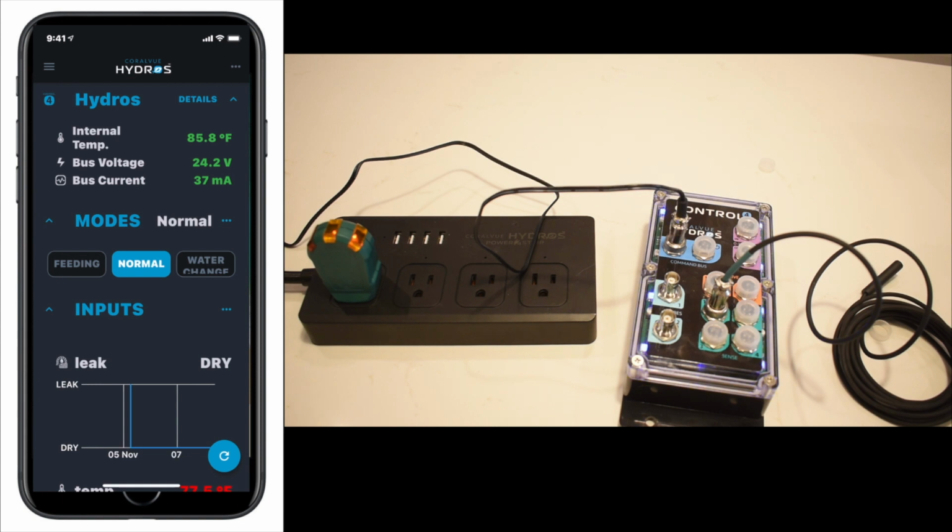The alerts come through really quick. So I did do a couple tests with losing communication or losing power. The alerts when you lose power to the power block are quite fast. They're probably within a minute. When you lose complete power to the whole unit, it took roughly 15 to 30 minutes to get an alert, so just be aware. I did test the leak detector, and when you do get water, it's immediate, so there's no lag in that.